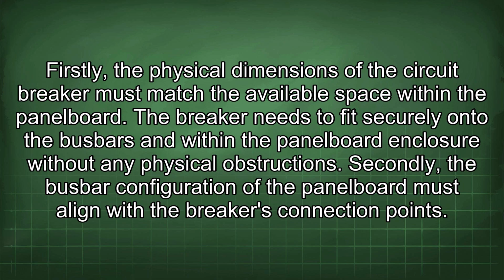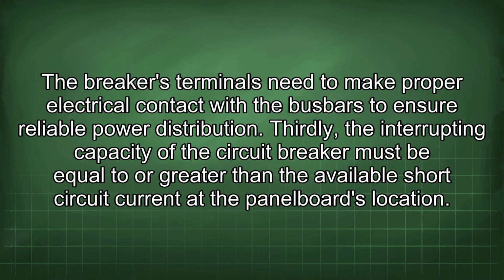Firstly, the physical dimensions of the circuit breaker must match the available space within the panel board. The breaker needs to fit securely onto the bus bars and within the panel board enclosure without any physical obstructions. Secondly, the busbar configuration of the panel board must align with the breaker's connection points. The breaker's terminals need to make proper electrical contact with the busbars to ensure reliable power distribution.